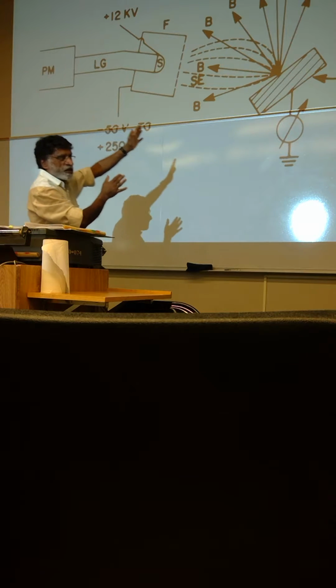Okay, everybody understands how the detector works? It's quite a complicated design, and it's very compact. It sits in a very small space, but all of these components are included in the detector. How does the photomultiplier work? Well, it basically counts the number of photons. Each electron, when it comes with a certain energy, generates a certain number of photons, and the photons are counted. There are different ways that the photomultiplier works, but basically it just counts them. Okay, so that's how your detector works.